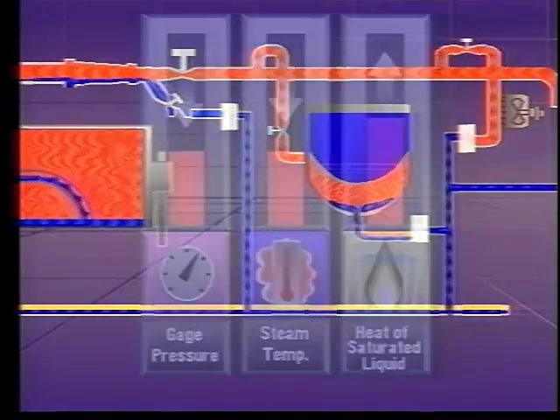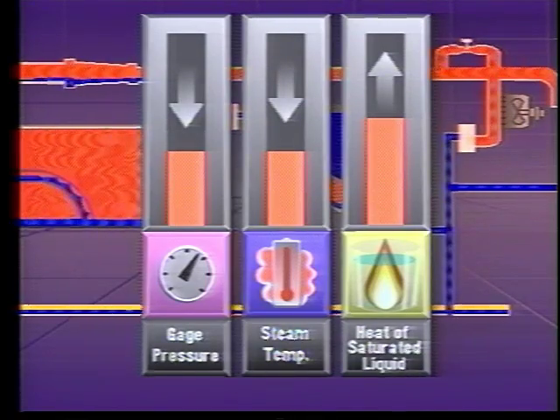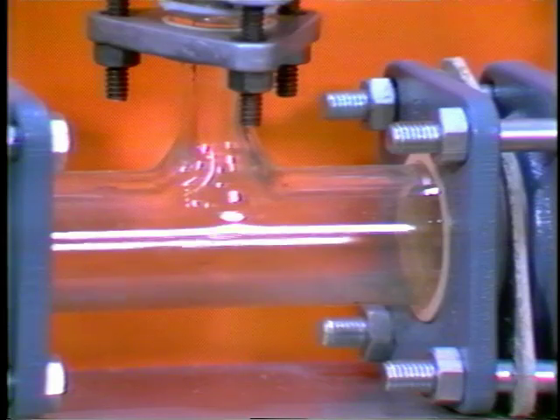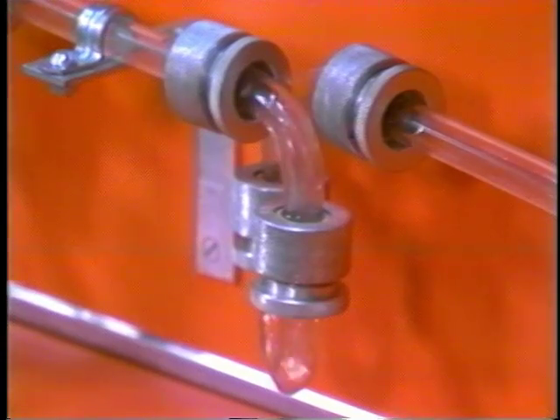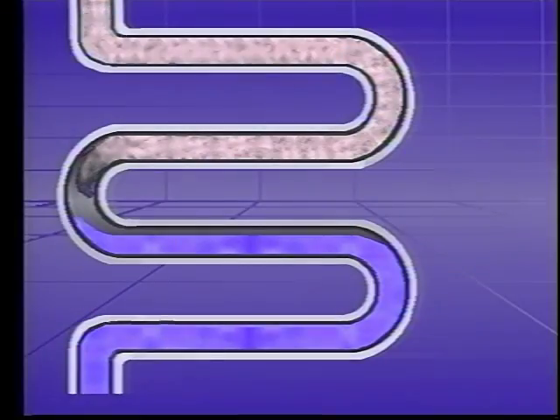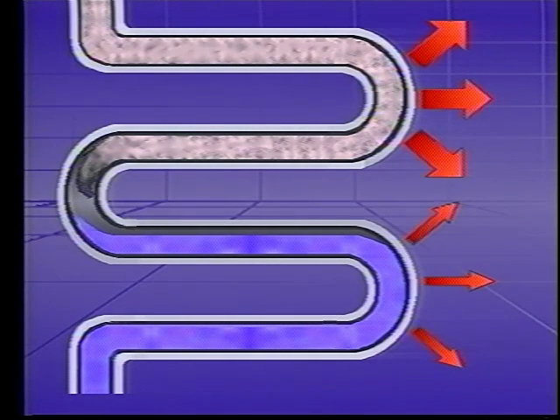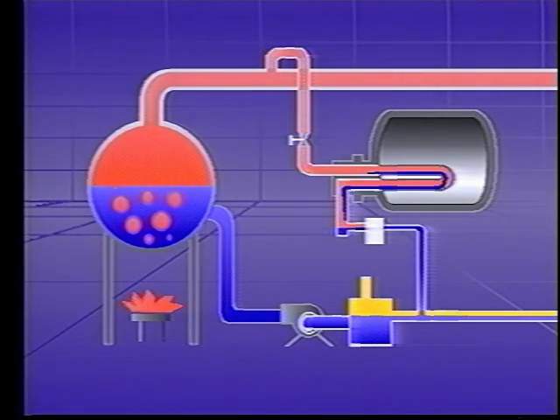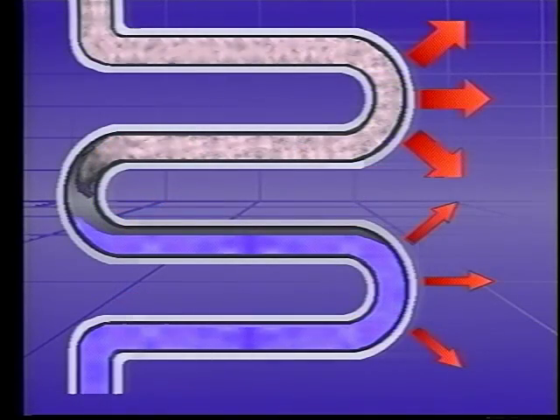While the temperature at 50 PSIG is only 298 degrees, there is more latent heat available for transfer. As the steam moves through the piping and equipment, it gives up its heat and condenses. Good condensate management is a necessity in an efficient steam system. As we've pointed out, condensate has much less heat to transfer than steam, so it should be removed from the system. In addition, if it is returned to the boiler while still hot, it conserves fuel. Condensate remaining in the tubes impedes the transfer of heat from the steam.